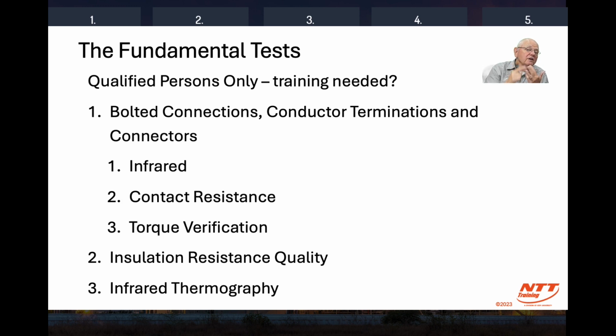And a third fundamental test says that we should be doing things like infrared thermography, right? Even with a small infrared camera like this, whatever you have. And you may well be doing your infrared thermography every year. So that's excellent. When it comes to checking your bolted connections, there are three methods that 70B says to use one of. Either get a torque wrench or screwdriver calibrated, and verify your torque connections; measure the contact resistance with a low resistance ohm meter; or use that infrared camera. While the equipment's operating, if you know what you're doing with infrared surveys, you can do an infrared survey to check for the tightness of bolted connections.